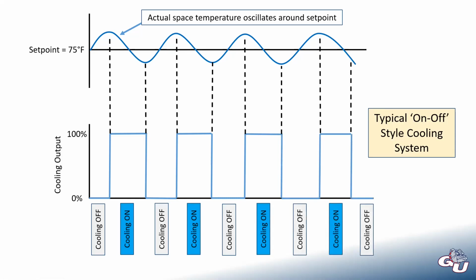Just on, off, and you get this decently wide swing of temperature around the point at which you want to maintain. So this could actually be going up to 76, down to 74. That wouldn't be that bad, but if you had wider swings, maybe plus or minus 2 degrees, that might not sound like a lot, but 2 degrees actually makes a pretty big difference for the perception and the comfort of someone in a space.